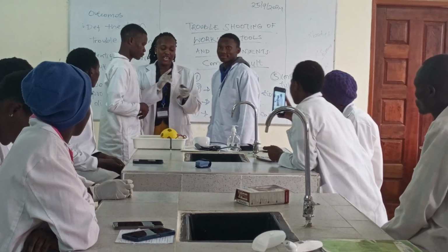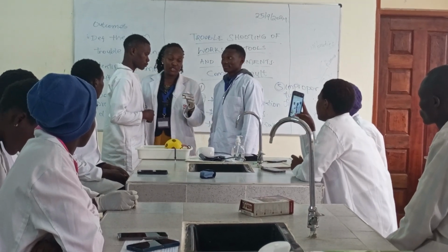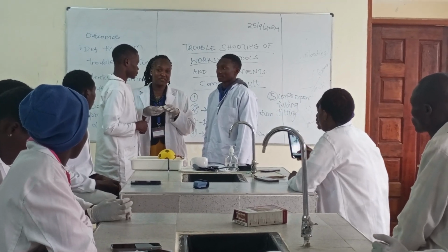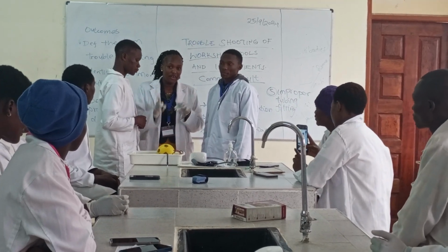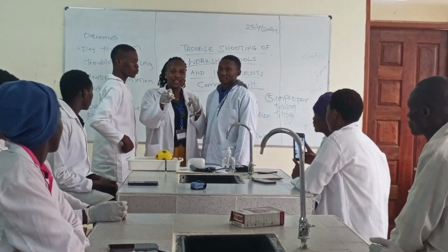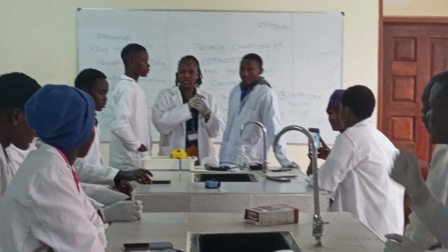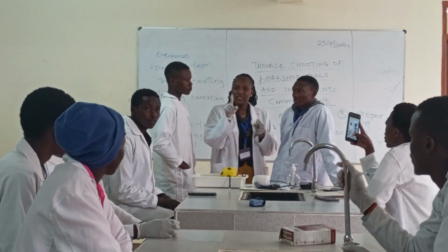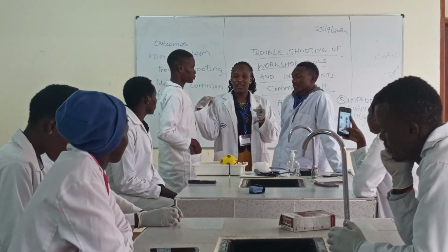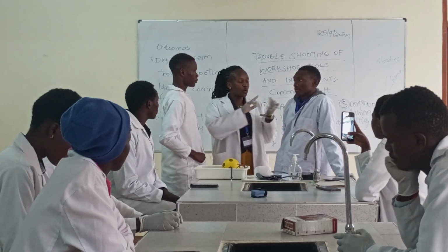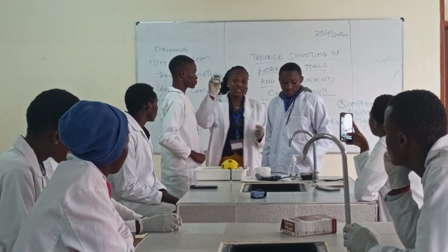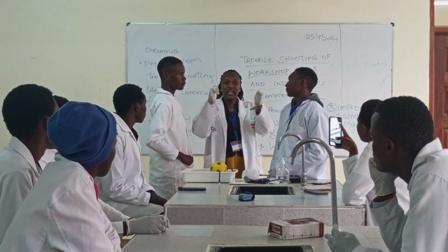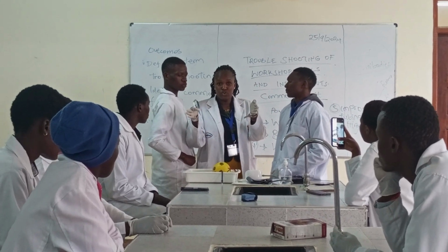According to their readings, when he tried to get the pulse of his patient, it did not give the correct readings. Why did it not give the correct readings? He removed the finger before the proper readings were done. So the machine has no problem, it's just that you did not give the equipment the required time to work.